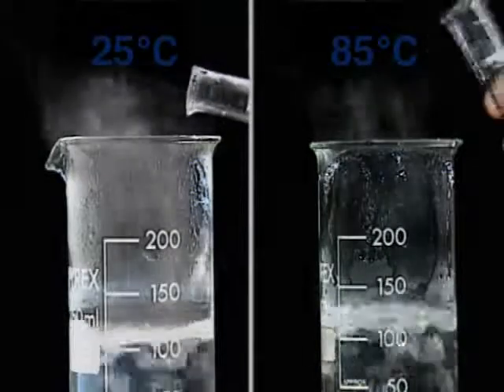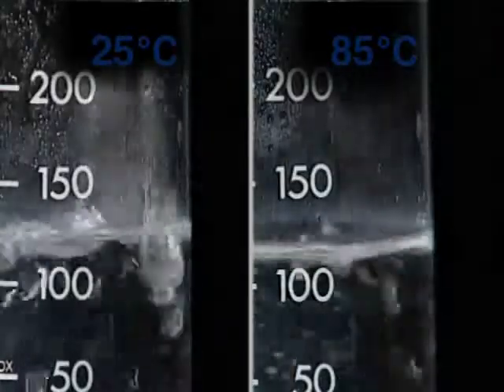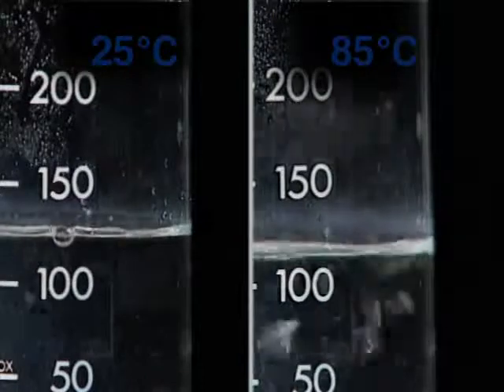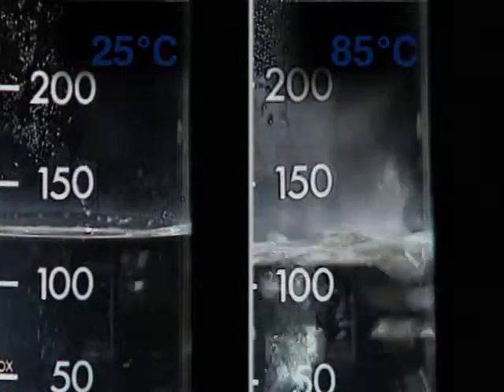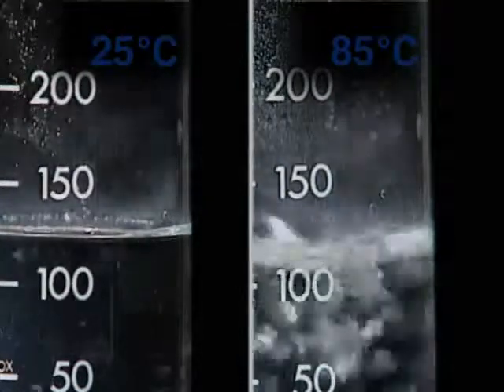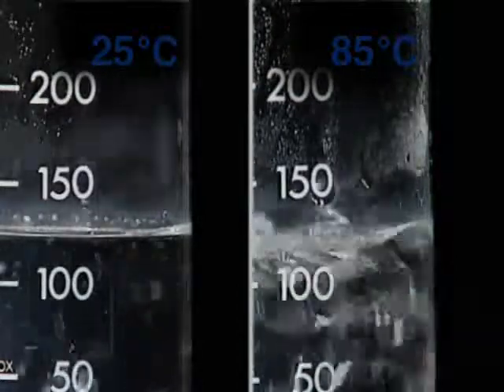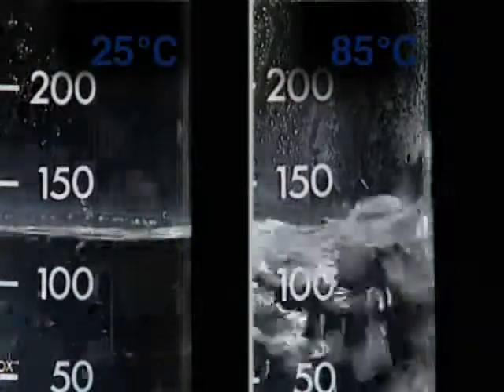These effects can be reduced by preheating the feed water. The higher the temperature, the quicker the boiling rate can recover. Higher temperature feed water also reduces the need for oxygen scavenging chemicals.